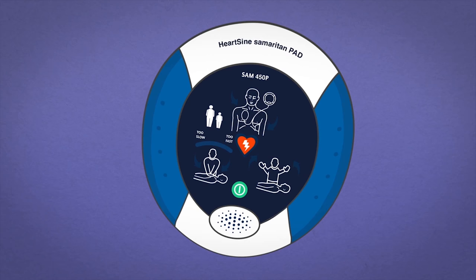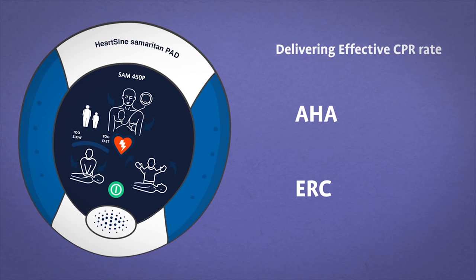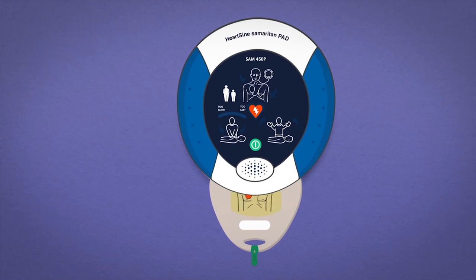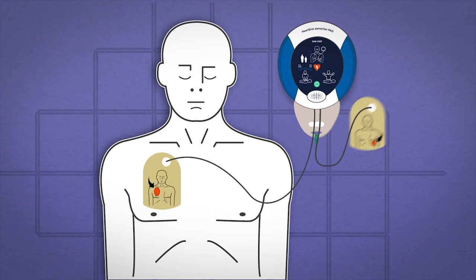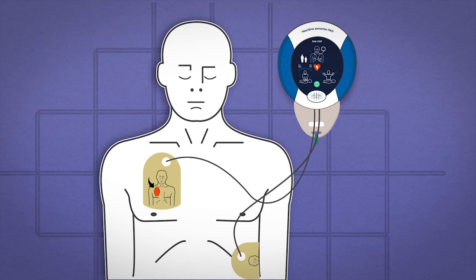CPR Rate Advisor helps ensure the rescuer performs CPR at an effective rate and at an optimal CPR fraction, in line with the American Heart Association and European Resuscitation Council guidelines. With its revolutionary technology, HeartSine's CPR Rate Advisor uses only the defibrillator electrodes to detect changes in patient impedance, rather than accelerometers or pucks commonly used in other AED solutions that provide some CPR feedback.